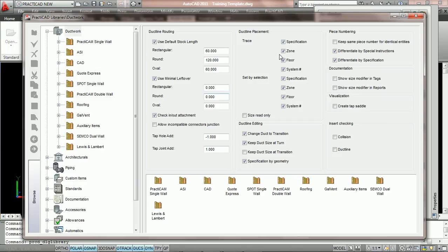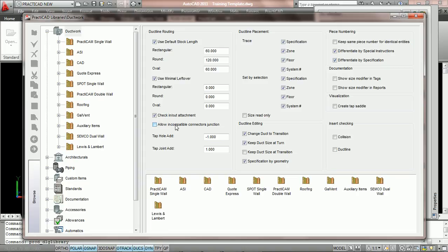And under duct work libraries, you have the option here to allow incompatible connectors junction. This option we recommend to always keep unchecked. When it's unchecked, we're not allowed to have incompatible connectors. So PractiCAD is automatically going to change the connections as you snap duct to duct. And it will only allow you to edit connectors that are compatible.